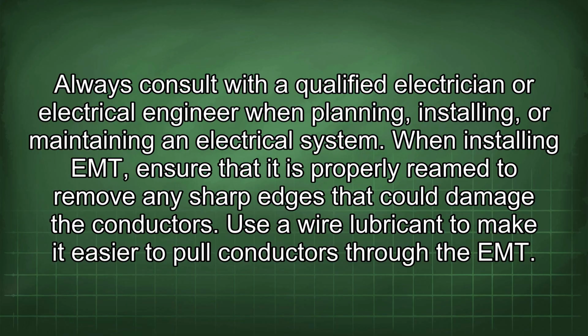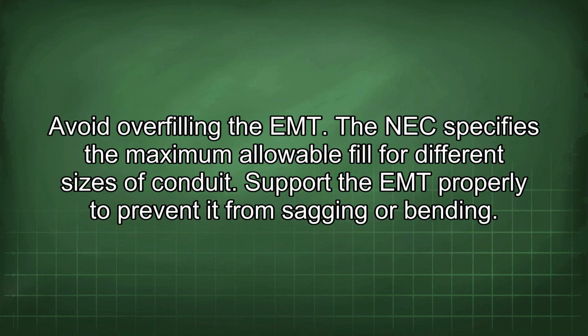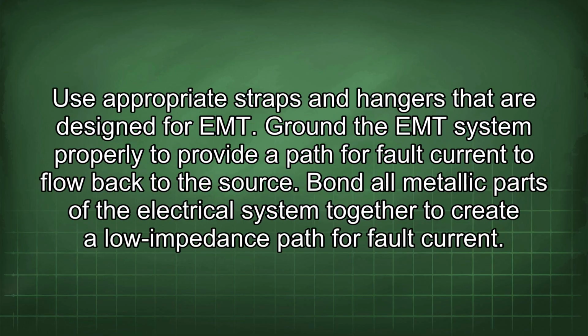When installing EMT, ensure that it is properly reamed to remove any sharp edges that could damage the conductors. Use a wire lubricant to make it easier to pull conductors through the EMT. Avoid overfilling the EMT. The NEC specifies the maximum allowable fill for different sizes of conduit. Support the EMT properly to prevent it from sagging or bending. Use appropriate straps and hangers that are designed for EMT.